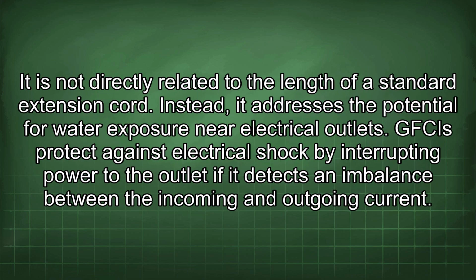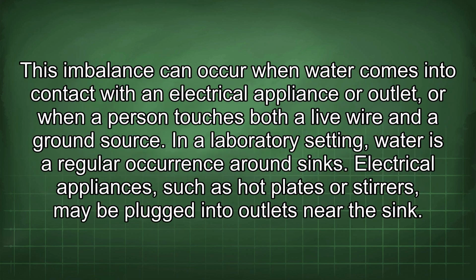It is not directly related to the length of a standard extension cord. Instead, it addresses the potential for water exposure near electrical outlets. GFCIs protect against electrical shock by interrupting power to the outlet if it detects an imbalance between the incoming and outgoing current. This imbalance can occur when water comes into contact with an electrical appliance or outlet, or when a person touches both a live wire and a ground source.